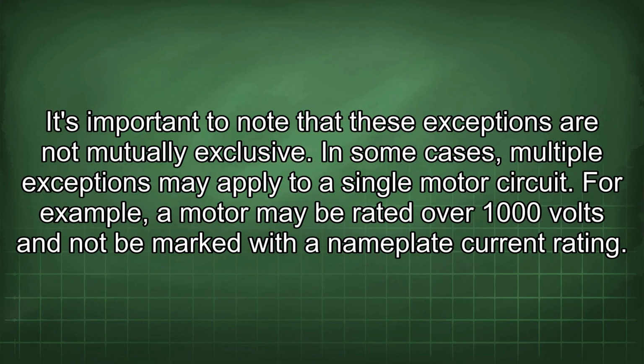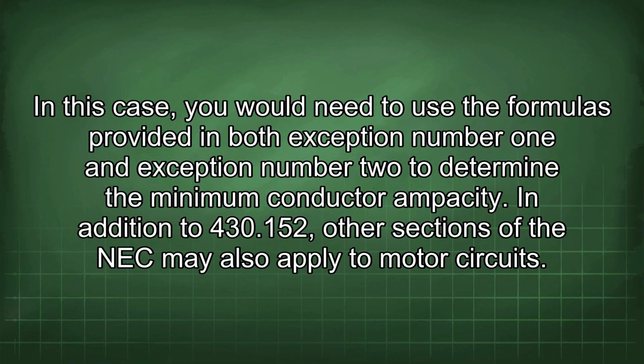It's important to note that these exceptions are not mutually exclusive. In some cases, multiple exceptions may apply to a single motor circuit. For example, a motor may be rated over 1000 volts and not be marked with a nameplate current rating. In this case, you would need to use the formulas provided in both exception number 1 and exception number 2 to determine the minimum conductor ampacity.